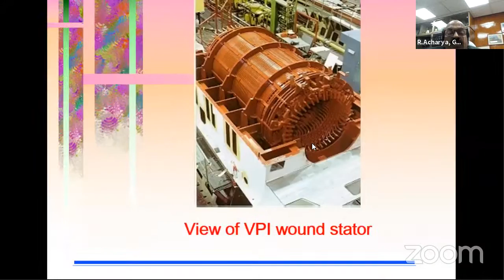A little quick look at the manufacturing process. What you are seeing consists of the stator core in which the winding is placed. So you can see here the stator core of large capacity machines. I have taken the view of the stator core under building of a typical 60 megawatt machine, wherein the man is standing in the bore and going on assembling lamination by lamination, a sector of lamination. And after the completion of that, the core looks something like this. It is ready for the winding.